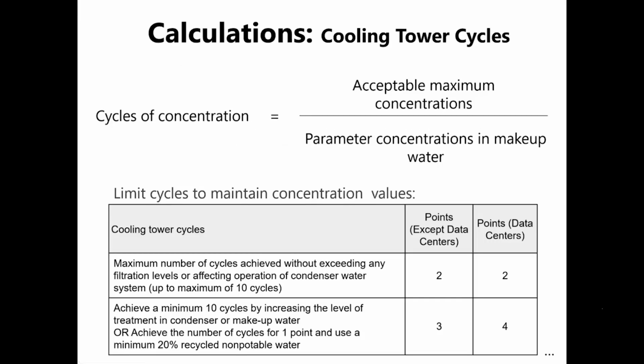The acceptable maximum concentrations divided by what's actually in our makeup water. So that's how many times we can run the water through our cooling tower. So if the maximum number of cycles achieved without exceeding the levels is 2, and then again, we want to remember that data centers are separate on this one as well. Data centers, where it comes to water, are often separate. And so if we achieve a minimum of 10 cycles by increasing treatment, or achieve the number of cycles for 1 point and use recycled non-potable water, then we get 3 points as well.